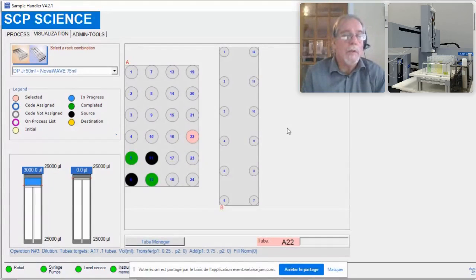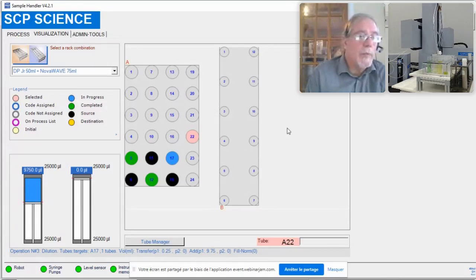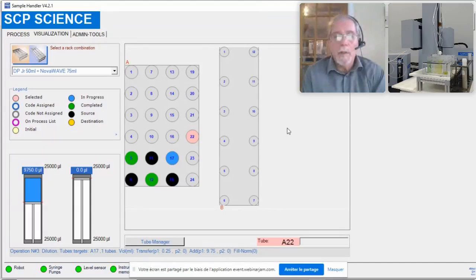So now it's rinsing the outside of the probe. Between samples, we rinse the outside of the probe. And now when it's rinsing the outside, the probe actually moves down into the wash station and then comes back up. So here we're picking up our diluent of 9.75 milliliters, then we'll pick up a 250 microliter or 0.25 milliliter aliquot of the sample after we stir it. And we'll dispense it in the tube behind.